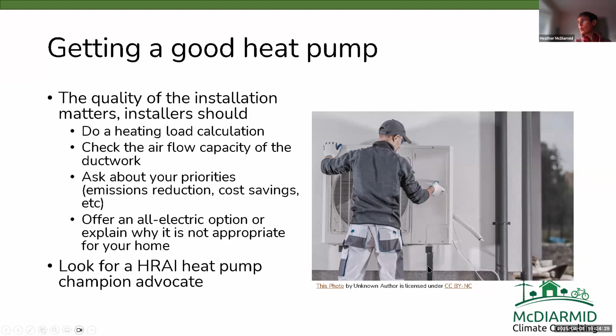If you want a good heat pump that provides the majority of the heat for your home, look for one that is cold climate rated, meaning it's designed to perform well at very low temperatures. For efficiency, look for the HSPF, the heating seasonal performance factor, version 2. We're in HSPF region 5, which just means a colder climate than most of the US, so you want greater than 6.6 in that region.